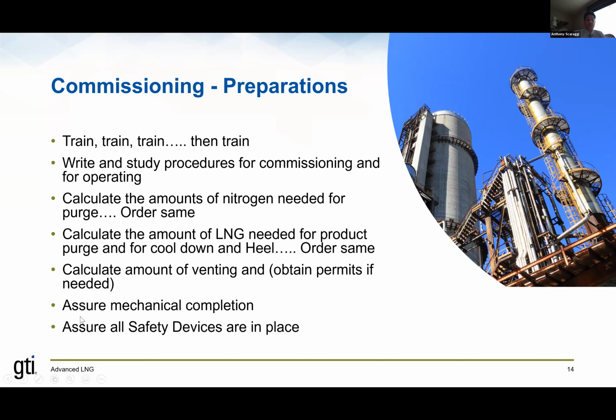Before you do any commissioning, you ensure that you've got mechanical completion of the facility, meaning that it's mechanically ready to have natural gas introduced into it. And you definitely have to be sure that all the safety devices are in place before you actually do commissioning. So these are some of the steps. There are many, many more, but some of the basic steps that you would prepare for when you're preparing for commissioning.